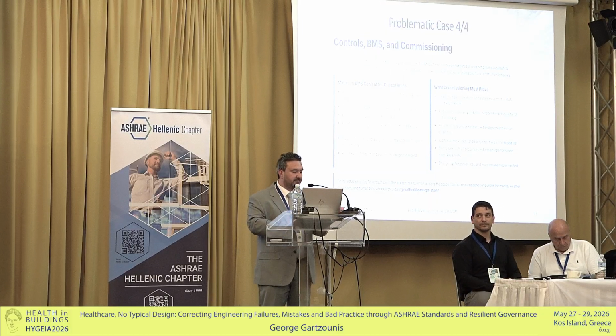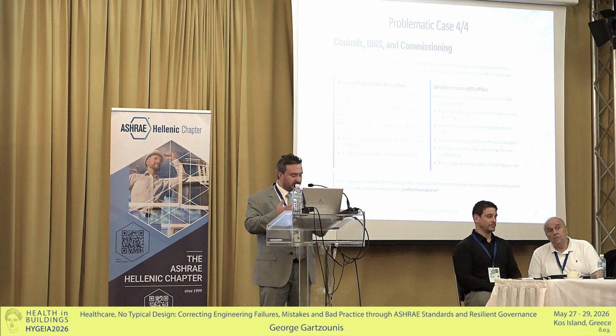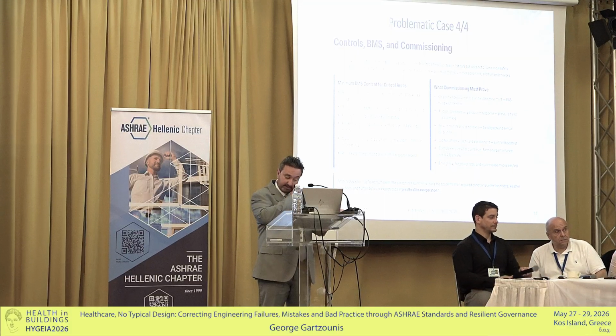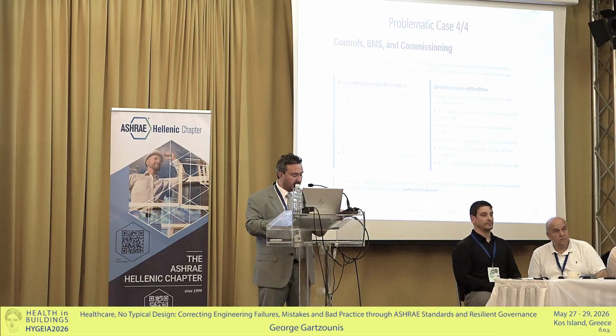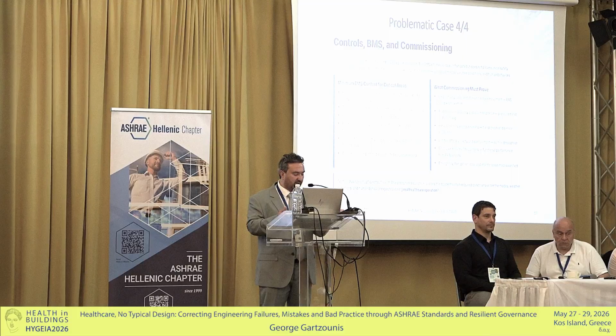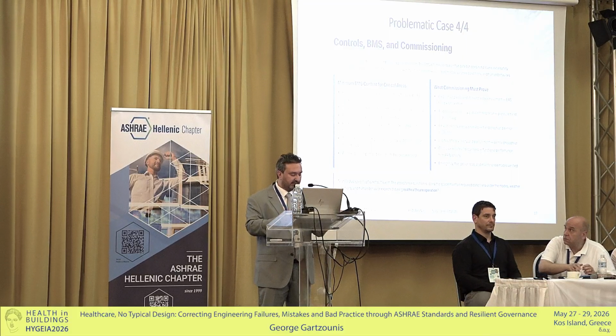Controls and BMS - all of that case was analyzed in the previous days. Controls issues are often where good design intent becomes poor operation. In many healthcare systems, the BMS records comfort data but does not prove clinical safety conditions. Critical rooms may have pressure sensors but no useful trends. Alarms may exist, but no one owns a response. Energy optimization may reduce airflow or humidity control without verifying clinical readiness.